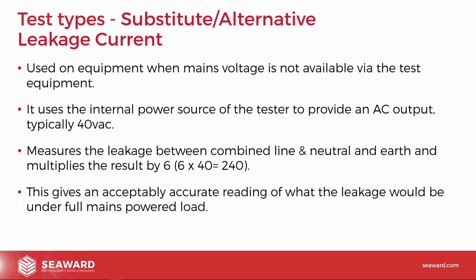All of these things will tell us about the condition of the insulation, and generally it's about understanding and applying the right ones at the right time. Have we got the right test for the right job to give us that picture of the insulation? Now, ideally, we do all of them, but obviously, it's what is reasonably practicable. What do we need to know to actually understand the faults posed by the equipment? And generally, that's where most people will pick one or two of these tests to carry out on equipment to make sure that we're getting that information and we're making sure the equipment is safe for continuing service.